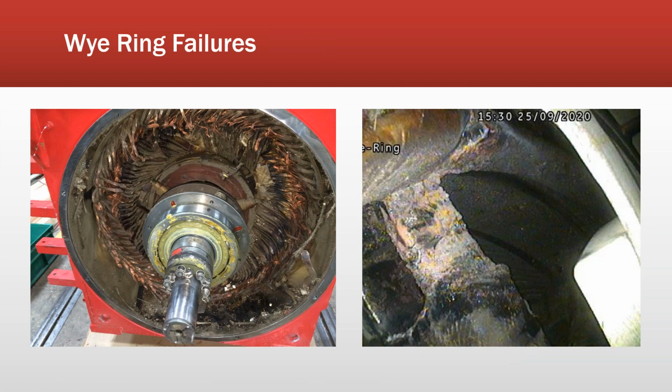So Y-rings. Well, on the left, that is a catastrophic Y-ring failure. Usually means that the generator is being replaced. The idea is to catch it before then. So that generally runs a cost somewhere to the tune of 150 to 200,000, not including all the energy losses while they're waiting for a crane, things like that. On the right, that was a fault caught just before failure.